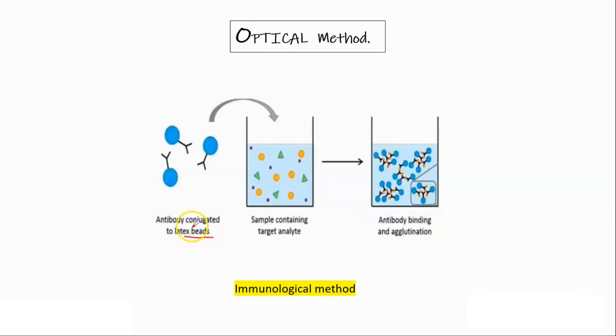Now the last method of optical phenomena involves the latex particles conjugated with antibodies. Now suppose you have factor 8 in your plasma and you have these particles. So when we mix these two reagents or with the sample, can I say this will occur, or agglutination will occur. So again when you pass the light through the solution, the optical density indicated is higher as due to agglutination or combination of antibodies and substance of our interest makes these complexes and the solution becomes more optically dense, and thereby we will measure its concentration depending on it.